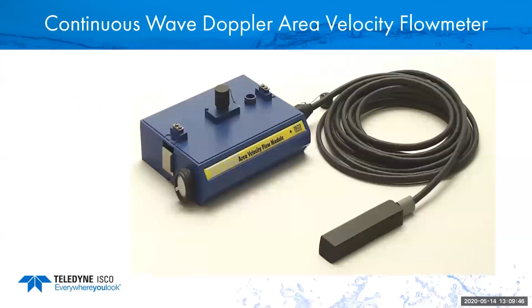This is an example of a continuous wave Doppler area velocity flow meter. The way these work: they wake up, they take a reading, they go back to sleep. It uses a continuous wave, transmitting a signal out the nose to measure the velocity and does some sort of a level measurement. In this case it uses pressure, but there are different methods of doing that - ultrasonic is another one. So you do a level measurement and velocity measurement to calculate the flow.